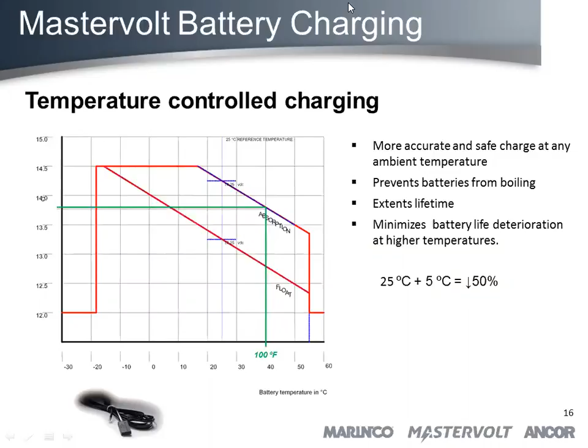It's not ideal because you're no longer sensing the battery itself. Right. Because at some point, ambient is one, but while you're charging and discharging, your battery starts to heat up too. So when you're recharging it and the battery is hot, that sensor will detect it. If it's not, you're only going to measure the ambient temperature. But it still functions, it will only measure ambient temperature. You don't want it on the top of the battery, do you? Because of the airspace, you want it on the side. I want it on the side, and preferably between batteries if you have multiple batteries side by side.